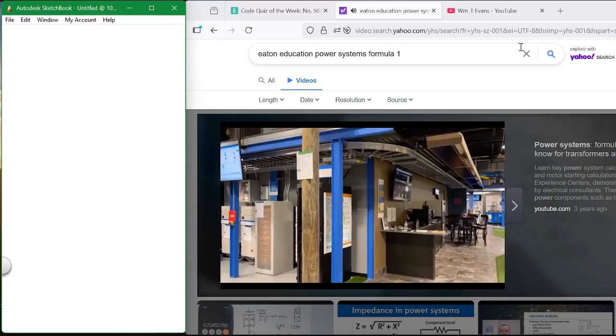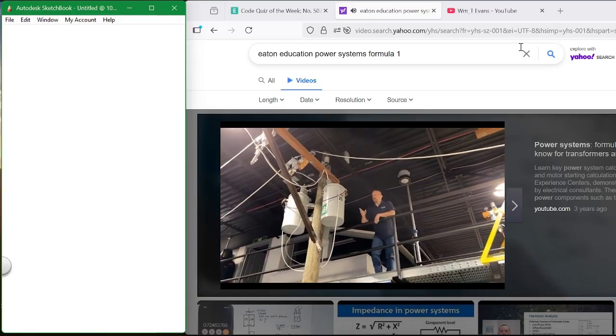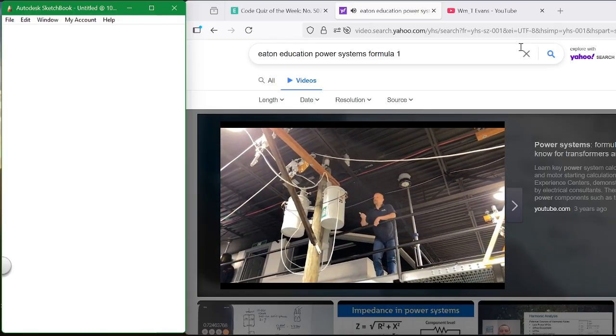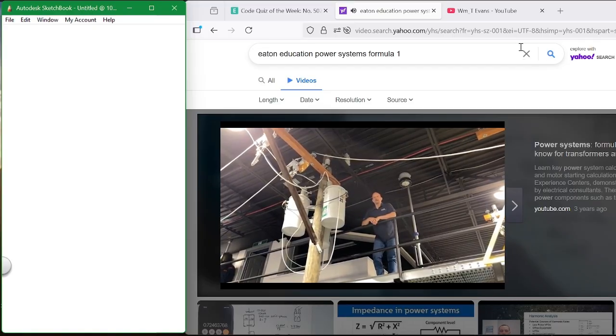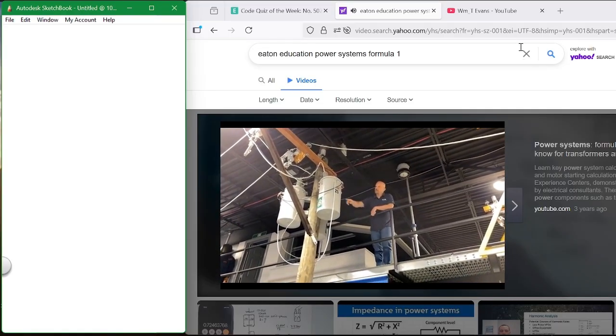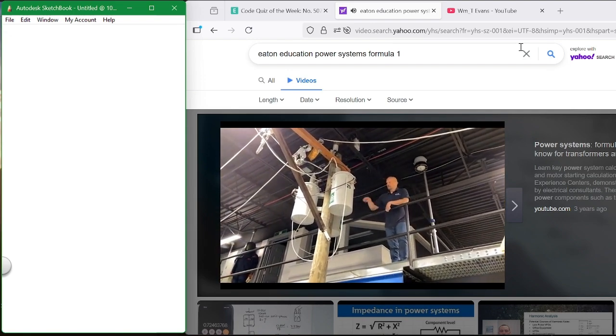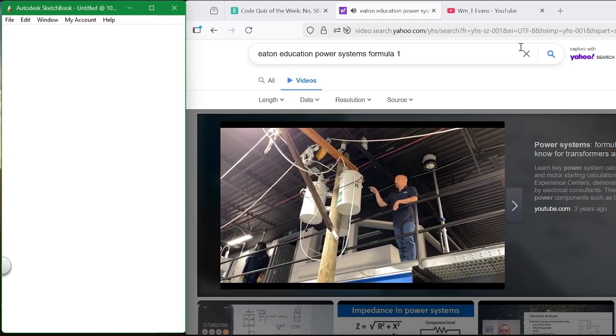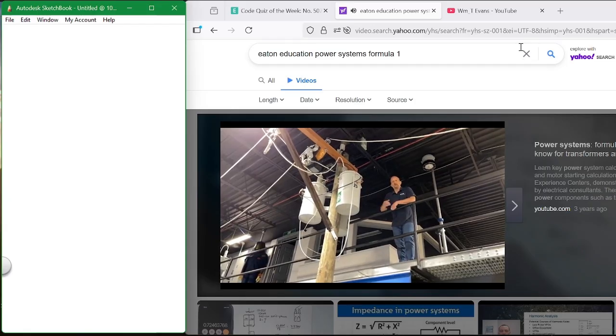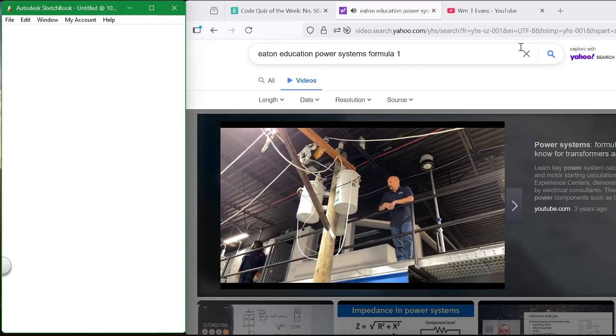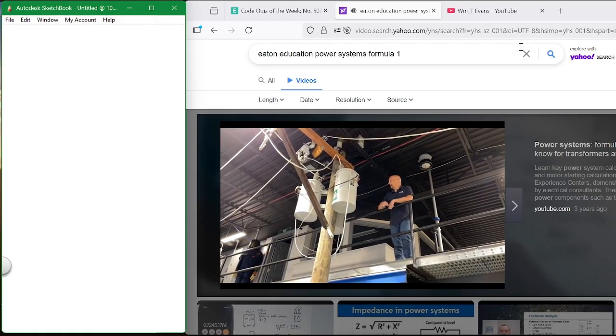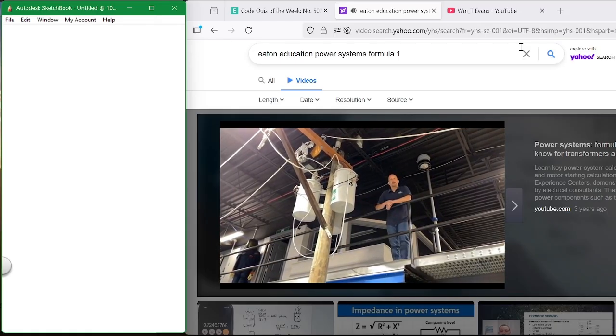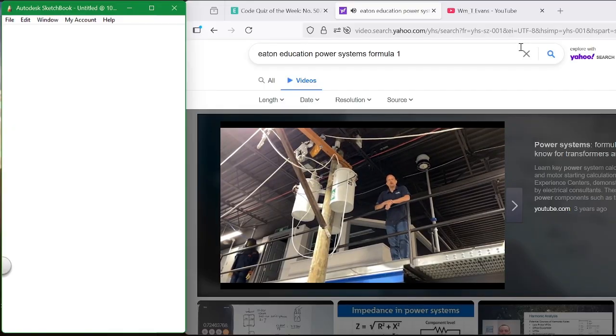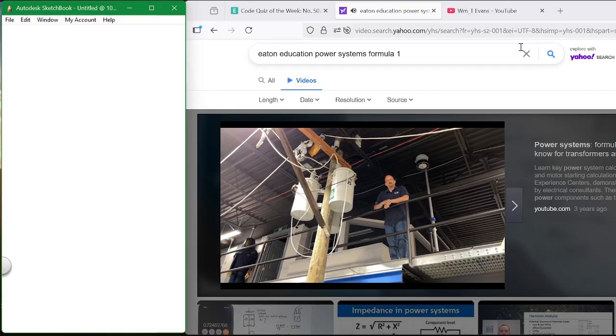So we're going to have to make some assumptions on this one. Hey, I'm up here. So these ones are a little different. Now, again, don't try this at home. I just happen to be up there because I know these aren't energized. But if you look at these transformers, it has 25 kVA. So three of them together make a bank in a delta Y configuration of 13,800 volts in this case to 480 volts, Y connected, so 480, 277. And this one's going to be solidly grounded. And I'm standing right up here next to the nameplate, so I'll show you a picture of the nameplate in the PowerPoint. But again, this is what you might see in front of a strip mall.